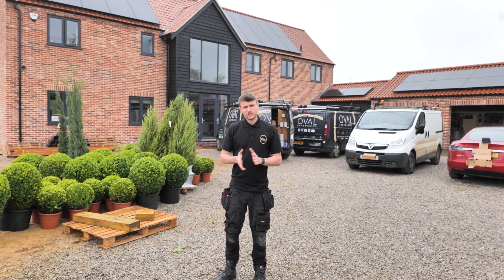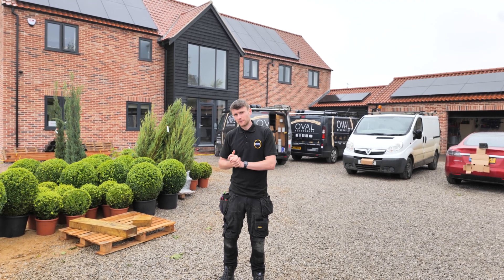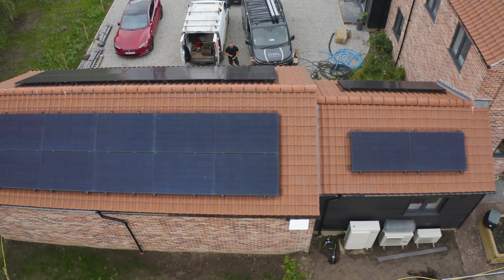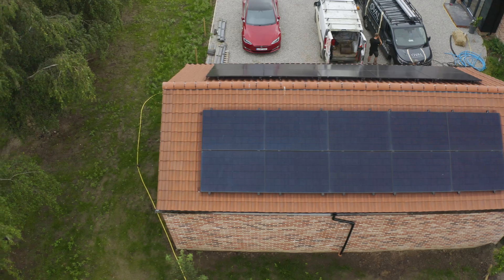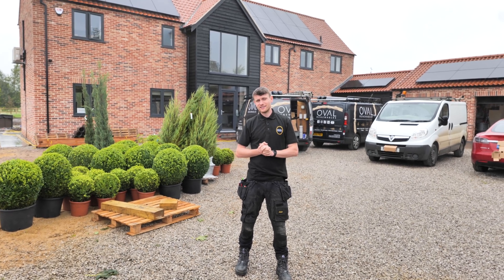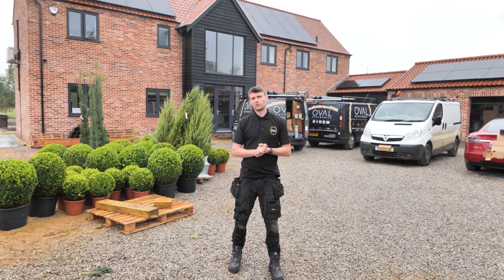We've made it outside — much like Rishi Sunak, I'm in the rain without an umbrella — but here are the panels. On the main house we've got 20 panels, two more on the little annex and another two on the other side of it, then ten on this part of the garage and another ten on the back side. That's 44 panels in total — the Perlight 430 watt panels, one of our favourites — giving about 18.92 kilowatt peak, all feeding back into that 10 kilowatt three-phase inverter.